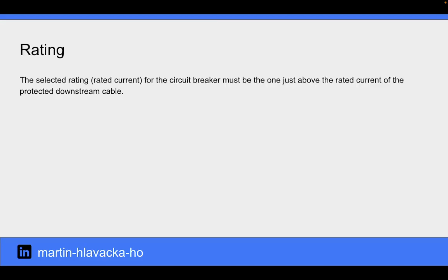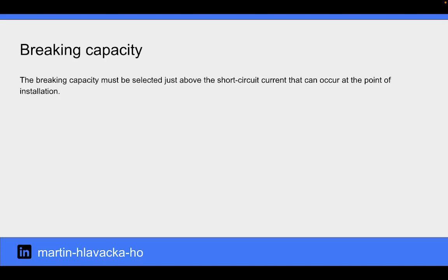The selected rating for the circuit breaker must be the one just above the rated current of the protected downstream cable. The breaking capacity must be selected just above the short circuit current that can occur at the point of installation.